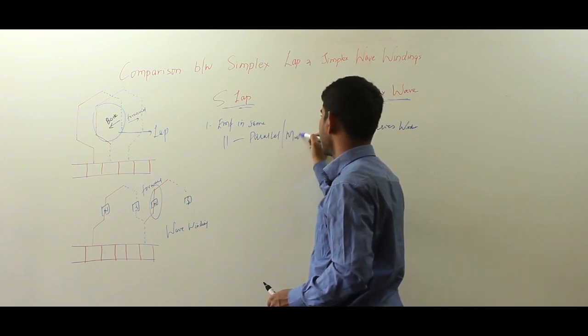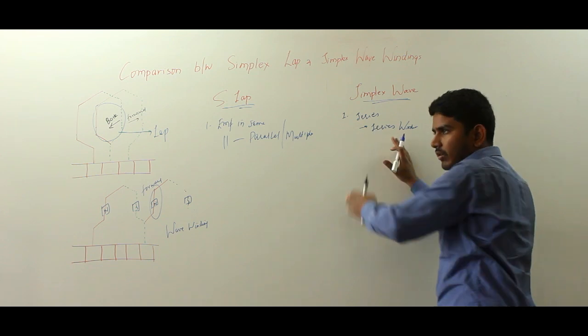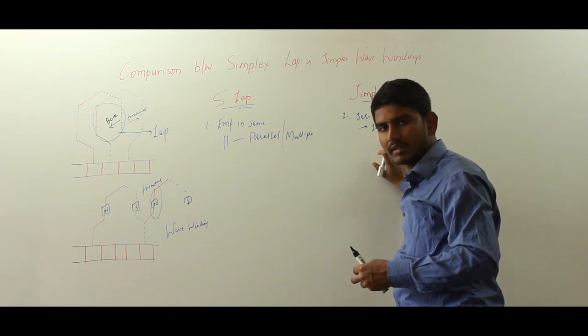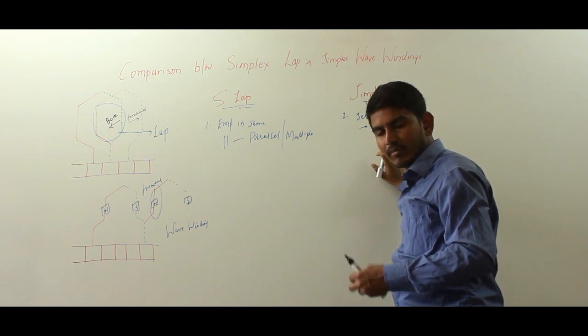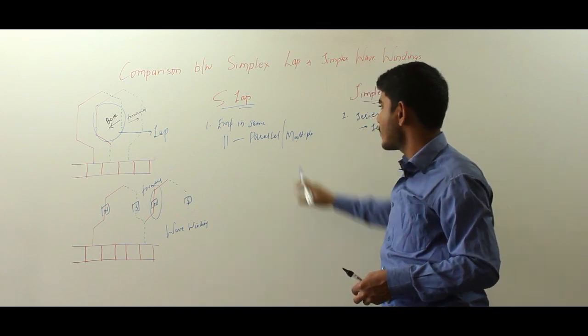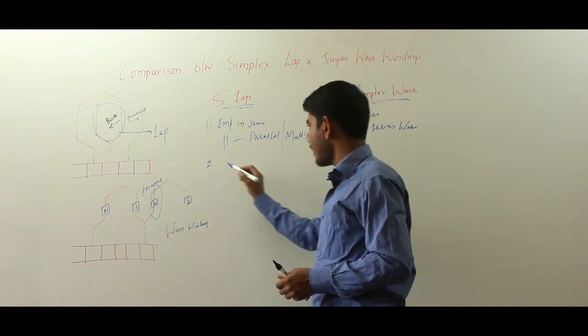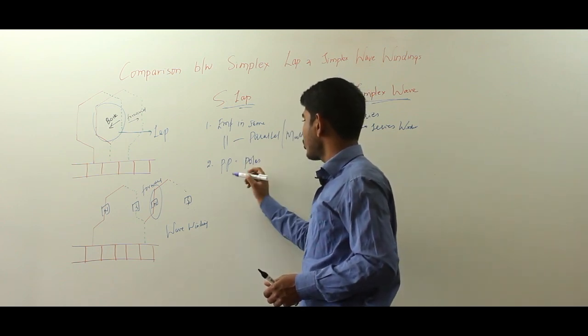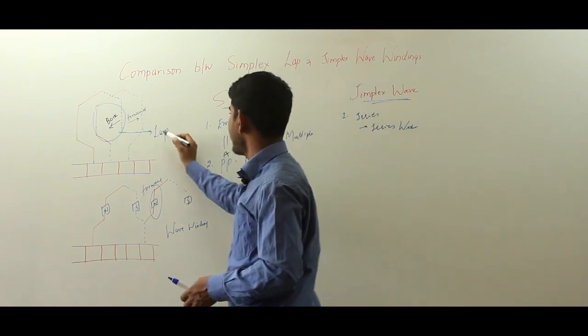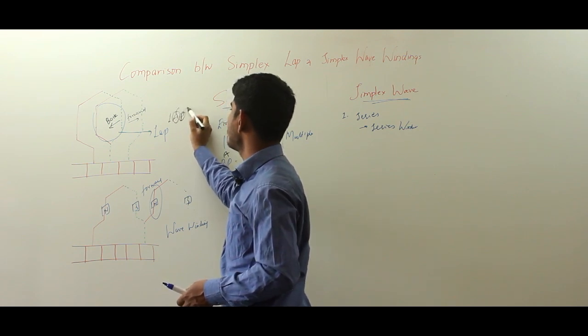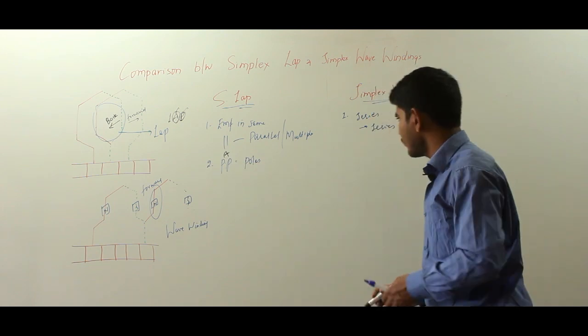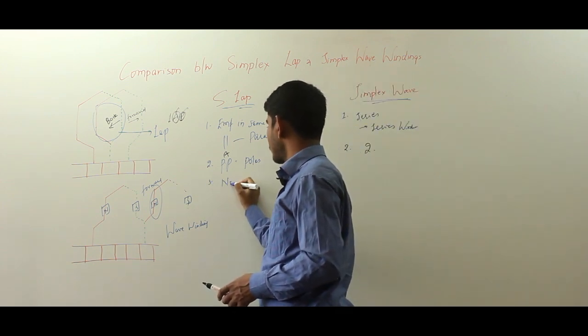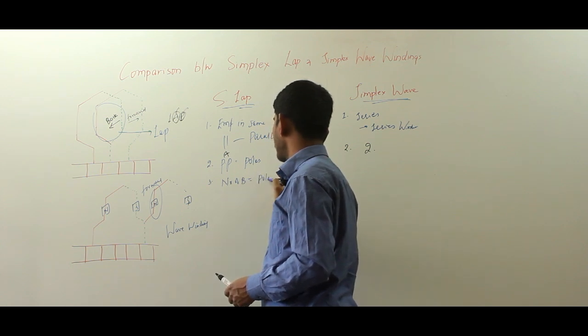Lap winding is also called parallel or multiple winding. Wave winding is a series winding where the current has basically two parallel paths — one path carries current in one direction and the other parallel path carries current in the other direction, but each parallel path carries current in the same direction and they are connected in series. The second difference is the number of parallel paths: in simplex lap winding, the number of parallel paths equals the number of poles. In simplex wave winding, the number of parallel paths is always 2.